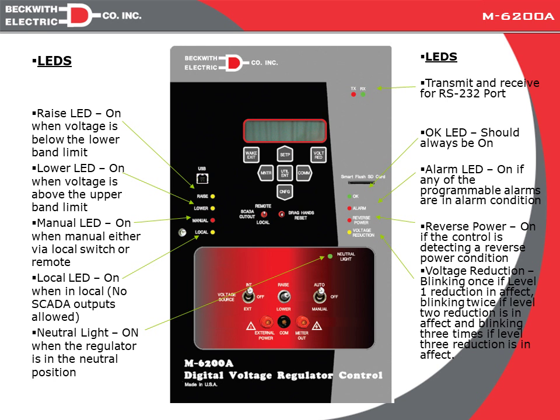Now, the raise and the lower LEDs, depending on the version of firmware you have, may either stay on solid at all times or they may blink. In the previous versions, they would be on as soon as you left band. So if we were out of band and calling for a raise, the raise light would be on solid, and it would stay on solid until the voltage came back into band. Same with the lower LED. On the newer versions of firmware, the LED will be blinking when it is timing towards the operation, and then once the time delay expires, it'll be on solid. But for previous versions of firmware, it is on solid even when it is timing.